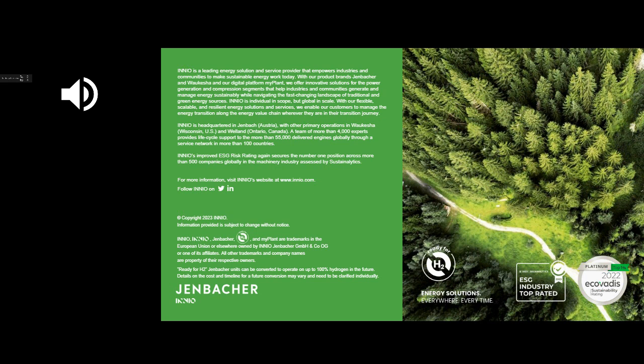Regarding the rate question, each engine for each fuel has a guaranteed rating. The same unit on 100% natural gas versus 100% hydrogen has a different rating. But a dual fuel unit like this one, with switching during operation, provides a full solution to reach a certain power level. Our maximum level with this type of solution nowadays is 1 megawatt. So when we deliver a unit, it's not that the engine rate changes when switching fuels - the full power commitment is guaranteed for any mix of the fuel.